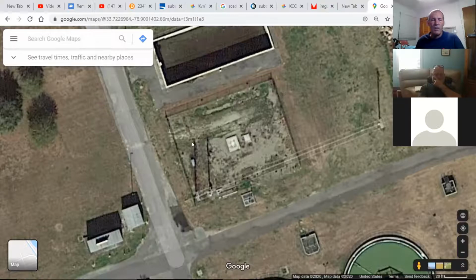The dispatchers are going to get a signal. We've lost the 34 kV line going to Grand Strand Water and Sewer. They're going to send an open signal to this switch. They're going to send a closed signal to this switch. The substation's back in service. Nobody even had to go to it. Now they'll send somebody, if that happened and I got called out, they're going to do all that manually. And somebody's going to have to go back out there and just confirm everything's going okay.